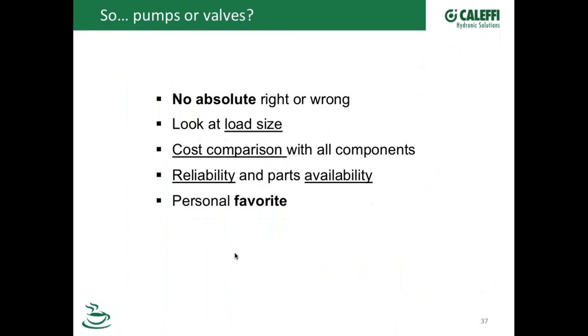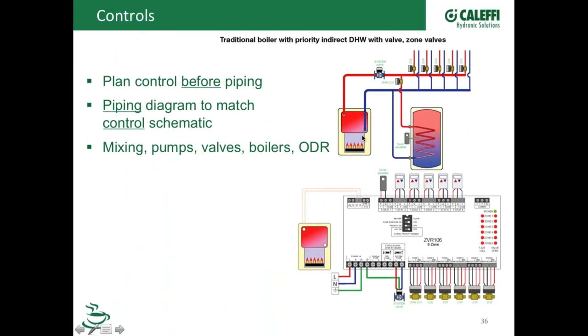I was going to say too, Bob, on all of our zone valve controls, when you open the cover, on the inside of that outer cover there's a QR code, and that QR code will take you directly to our comprehensive wiring guide. You might be thinking, why on earth don't we include this wiring guide with all of the zone valve controls? It's because it's a roughly 50-page document with color diagrams and the whole nine yards, just like what you see on this slide. So if you're doing something above and beyond a standard, really simple zoning system with pumps or valves, make sure to scan that QR code and look it up on your tablet or smartphone.